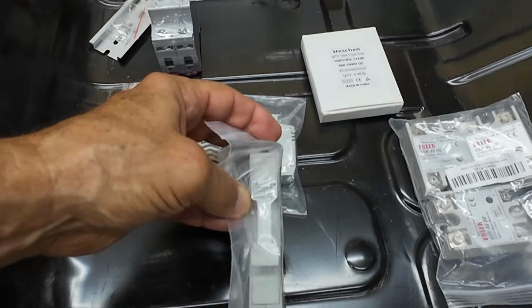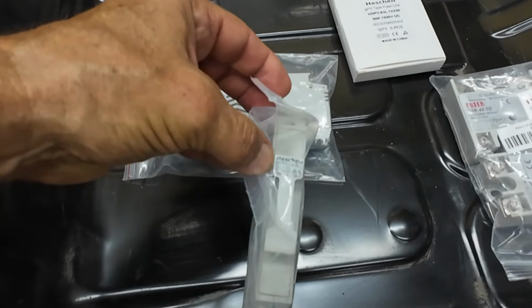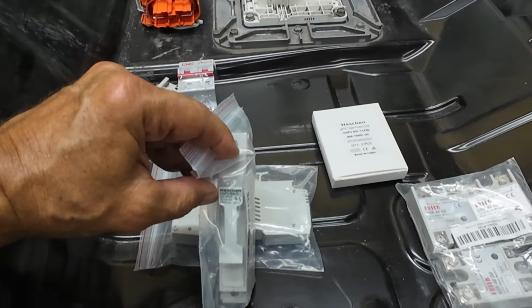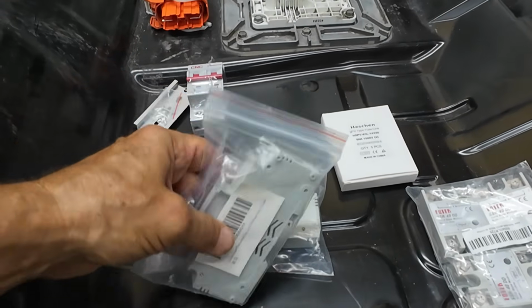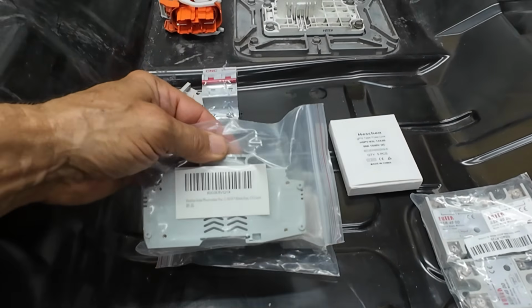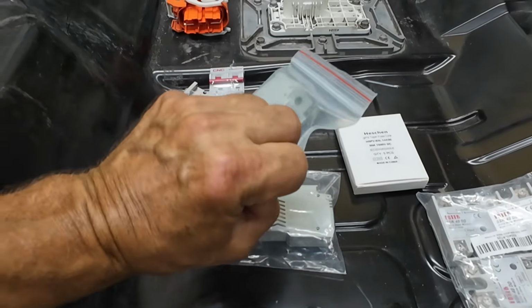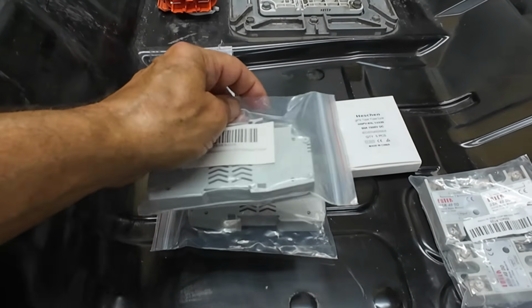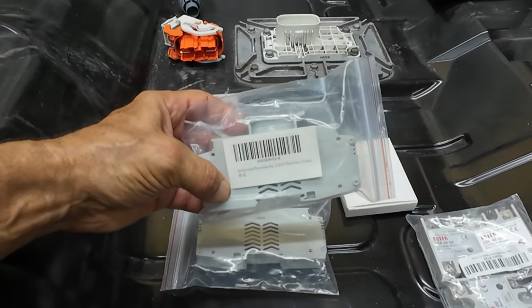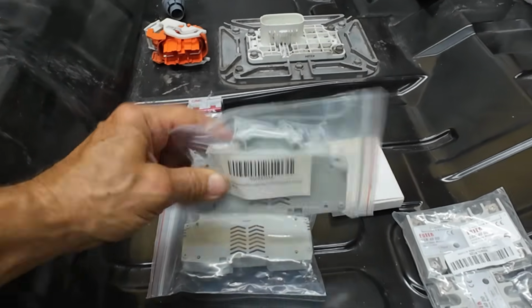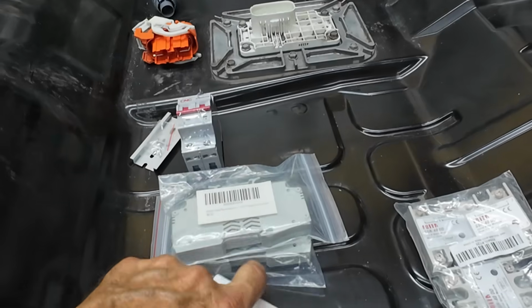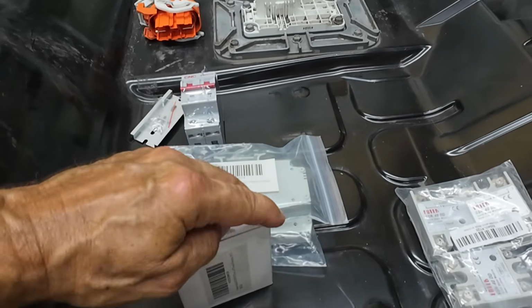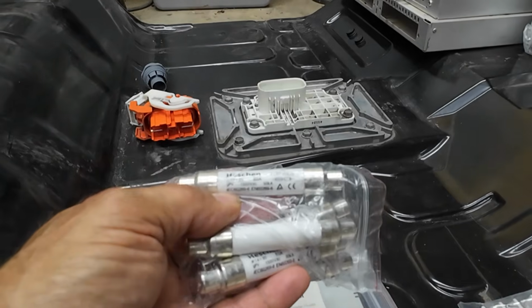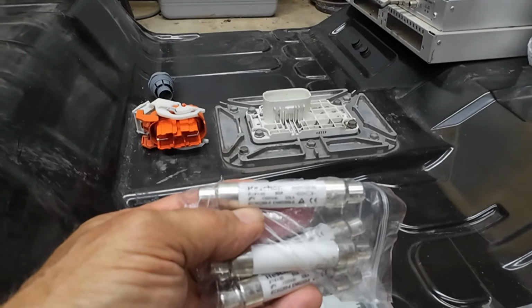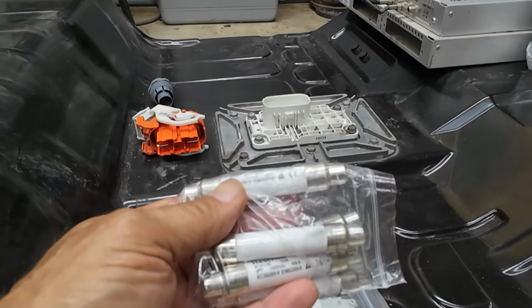These are good for up to 50 amps at 1500 volts DC. I went for the bigger ones, these are 85 millimeter holders, because they'll run up to 1500 volts. They take the 85 millimeter fuses, and these are 50 amp, 1500 volt DC rated fuses.